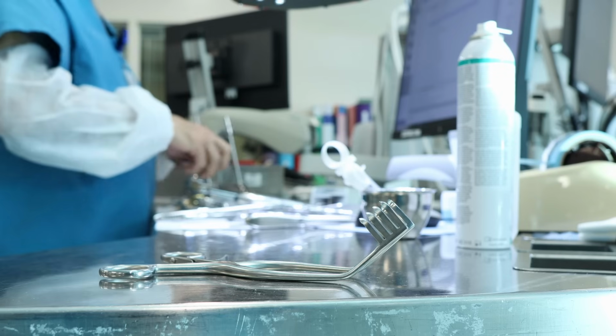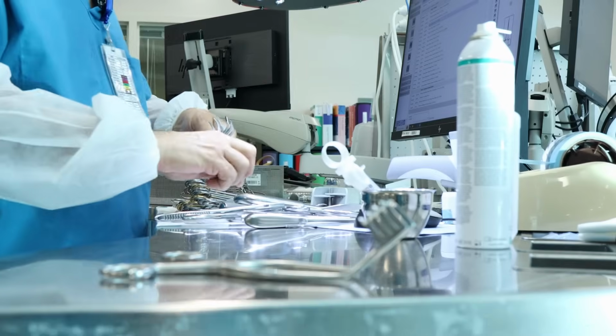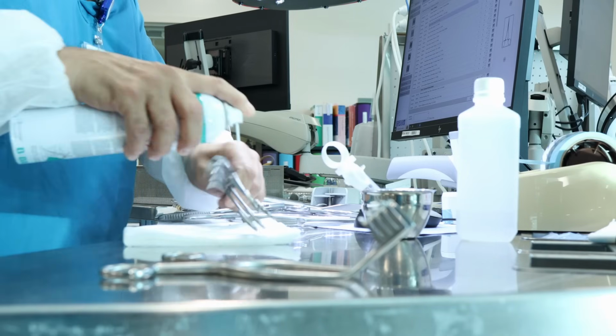Next in the process is testing functionality. Are the hinges of the instruments working properly? Are all the screws secured, if any are present? We are also testing sharpness for instruments like scissors. We are testing insulation integrity for laparoscopic instruments, and performing any other inspection necessary for the different types of instruments we are inspecting. Next is maintenance or lubrication, depending on the type of instrument and the manufacturer IFU. And lastly, the counting process for each instrument for each tray.